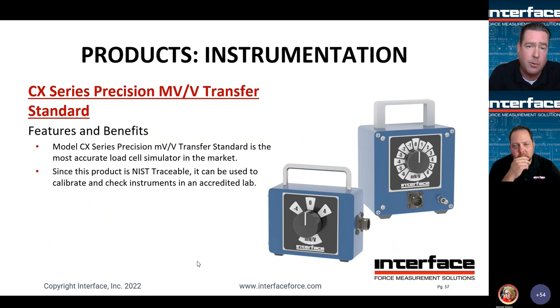So we've got 2 of them pictured here. We've got a 2-step, which is 0 and 4 millivolts per volt in both directions. And then we've got a 6-step, which is essentially decrements of 1 millivolt per volt up to 6 millivolts in either direction. Again, these can be used for scaling different instrumentation, and if traceable to NIST, you have essentially a traceable measurement standard that you can use to scale instrumentation.